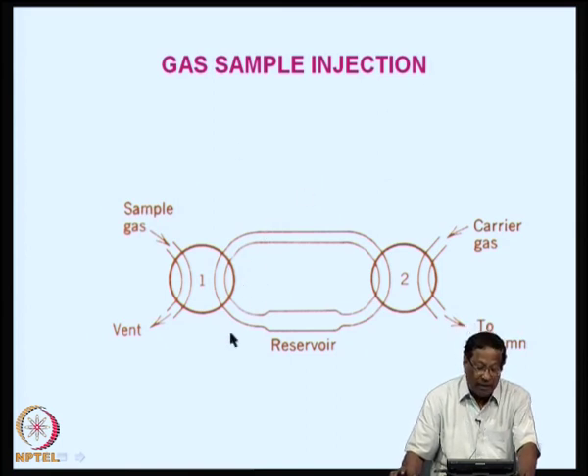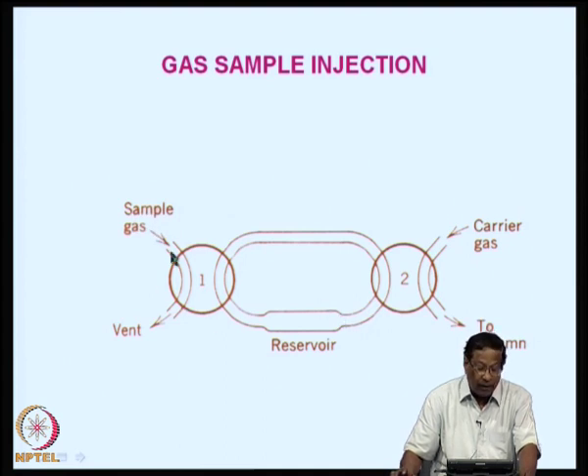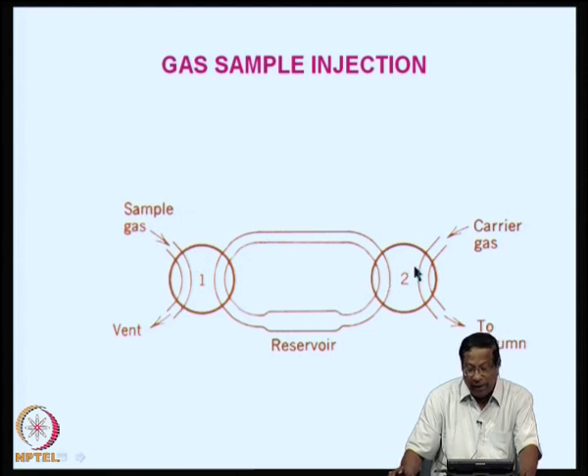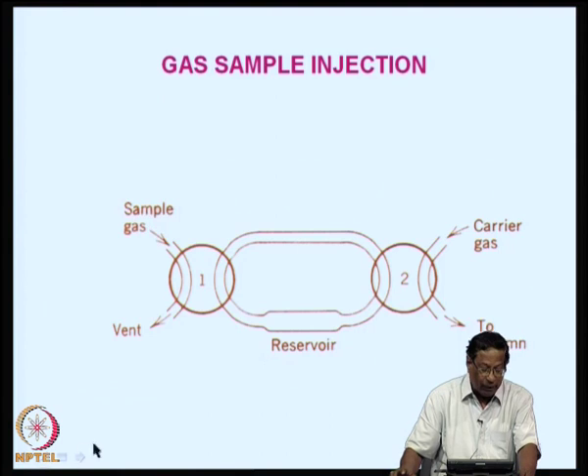For gas sample injection through a valve and loop arrangement, the sample gas comes in and is collected in a loop. The carrier gas is also passing through. Whenever gas is collected here, the carrier gas takes it as a plug and carries it directly through the loop system into the column.